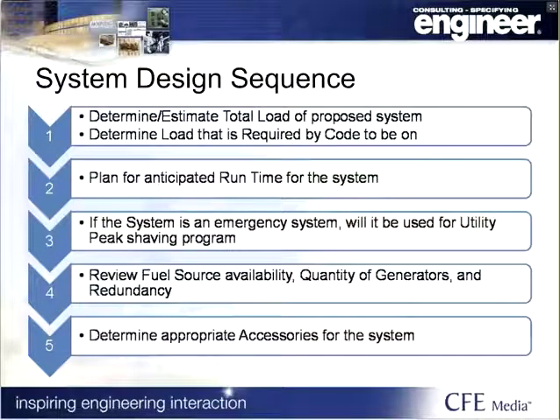Second step, you're going to start to think about, in my location, how long will I have to run for? I do a lot of work in Florida, where we have a huge risk of hurricanes, and a lot of facilities I do work at may have to run as long as 7 days without the grid being available. So it's an important consideration that their generators need to be capable of doing that.